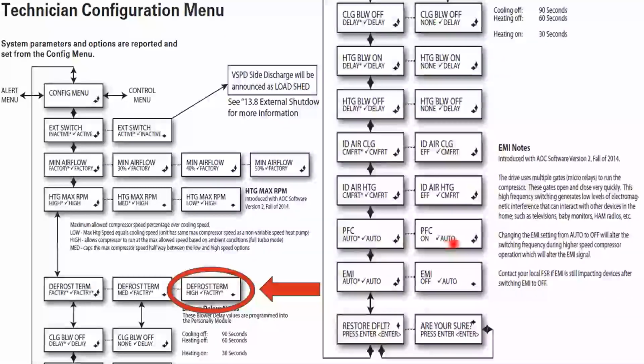PFC is power factor correction. You shouldn't have to touch that. That's for limiting your compressor. Your EMI: we've had some flickering light issues, so you can try to select EMI off. Changing the EMI setting from auto to off will alter the switching frequency during higher speed compressor operation, so it's going to affect the compressor when it's at 90 to 100% compressor speed. And then you can always restore default if you've gone through settings and need to.